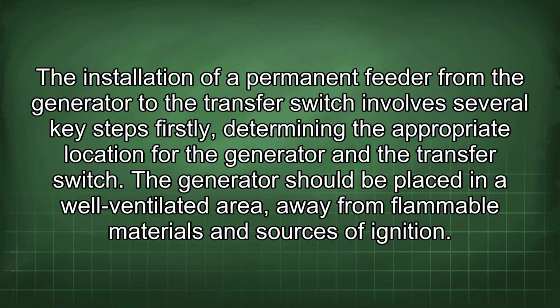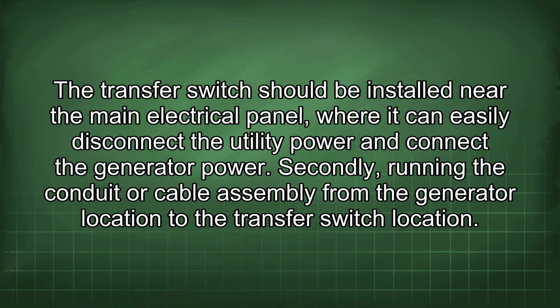The installation of a permanent feeder from the generator to the transfer switch involves several key steps. Firstly, determining the appropriate location for the generator and the transfer switch. The generator should be placed in a well-ventilated area, away from flammable materials and sources of ignition. The transfer switch should be installed near the main electrical panel, where it can easily disconnect the utility power and connect the generator power. Secondly, running the conduit or cable assembly from the generator location to the transfer switch location.